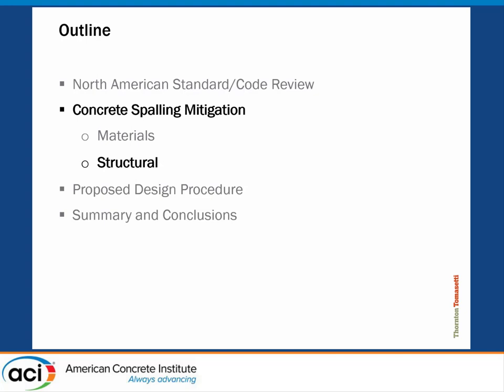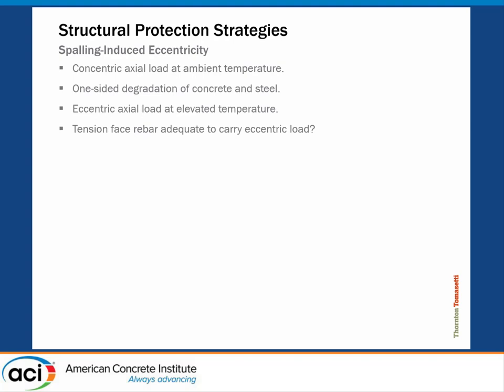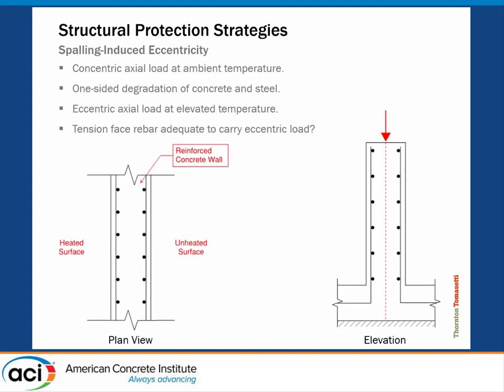From a structural standpoint, even if we mitigate the risk of concrete spalling as much as possible through mixture optimization, you could still have spalling. So there are things we can do structurally: if spalling does happen, let's cover the loads induced by spalling up front. The first is spalling-induced eccentricity. For a standard concrete wall with a one-sided fire, you get unsymmetrical degradation of concrete and steel. The fire-exposed side loses significant strength and the rebar degrades, while the unheated surface is perfectly fine. But the axial load remains concentric to the original cross-section from ambient conditions.